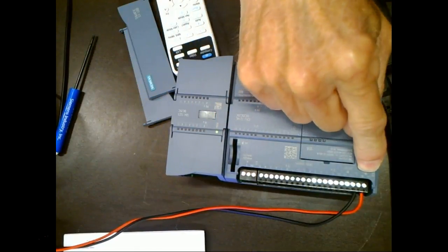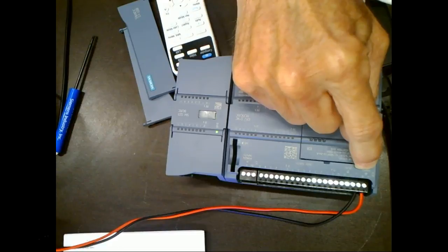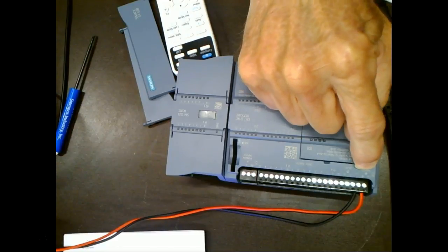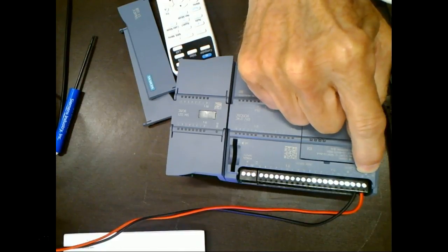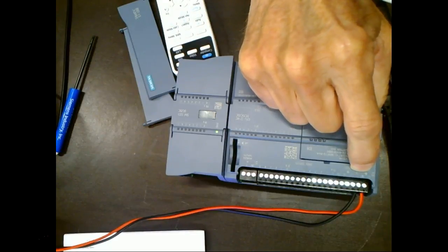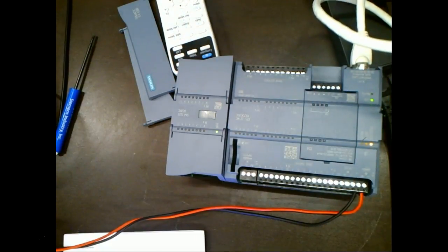Now, mine's upside down from yours. So we're looking at the arrow pointing in, right? Not the one pointing out, the one that's pointing in. Then you're gonna hook up the orange to L plus, and then your blue, you're gonna hook it up to M, on the arrow pointing in, not on the arrow pointing out. That would cause all kinds of problems.